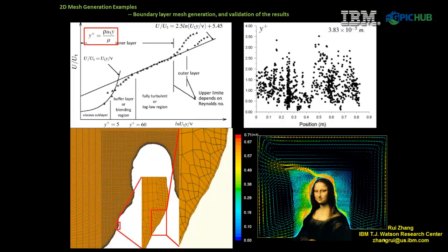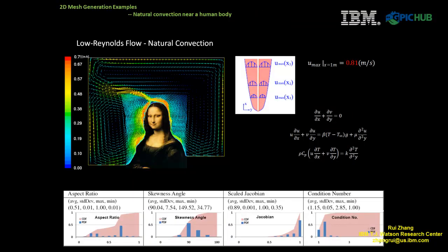The maximum velocity of the buoyancy flow is about 0.7 meters per second above the human height. Analytical solution of buoyancy flow near a flat plate was also developed to validate the CFD simulation. The analytical model shows that the maximum velocity would be 0.8 meters per second, which is very close to the CFD simulation result of 0.7 meters per second, and which helps to validate the CFD simulation. The mesh also shows good quality in terms of aspect ratio, skewness angle, scaled Jacobian, and condition numbers.